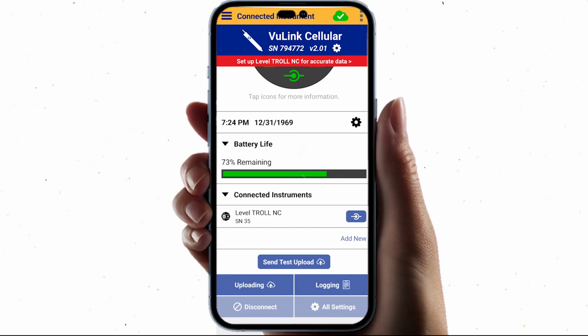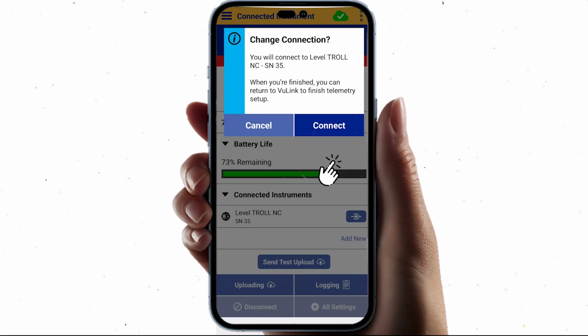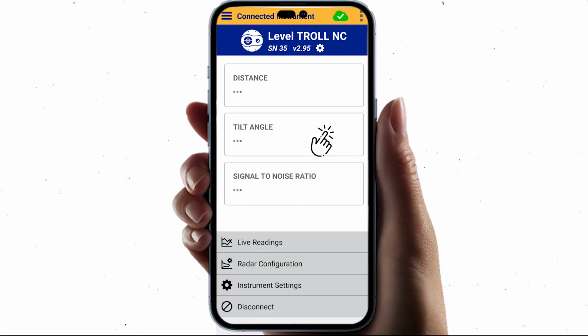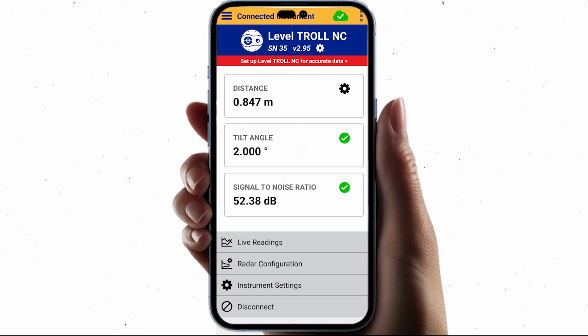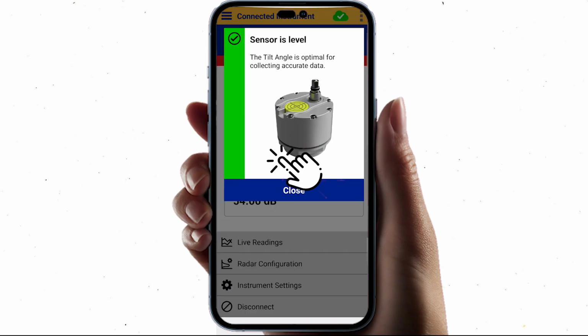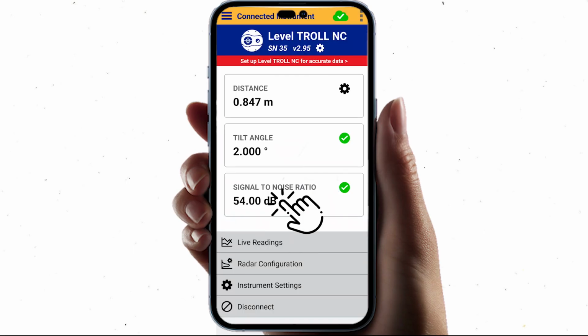If you are using VuLink, add the instrument in VuSitu. Then tap the instrument to connect to it. On the main connected instrument screen, you can view the current distance reading, tilt angle, and signal-to-noise ratio. These parameters can help you tell if the instrument is set up correctly. The app will show you if there are warnings or errors for any of these readings. You can tap each parameter to learn more or troubleshoot any issues.